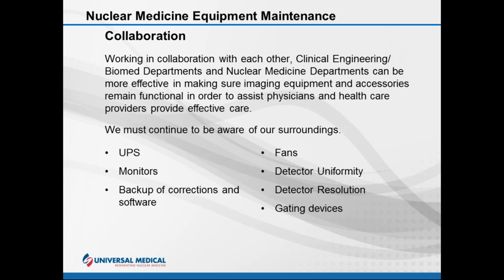Well, if you change out an inexpensive fan, it helps that board to stay alive. So again, being preventative, change out fans. Be sure on your gating devices, those little wires, they're being put on and off all the time. I always advise nuclear medicine to order a second set just in case. Without that, they can't get the ejection fraction. Backing up all of your corrections and software is extremely important.